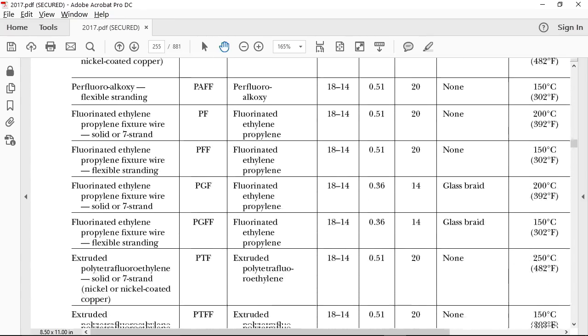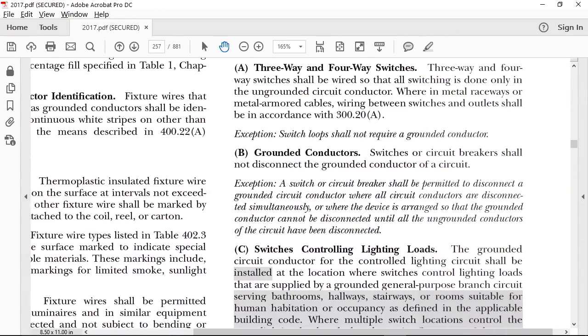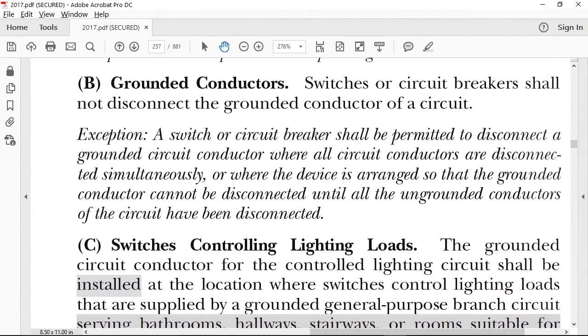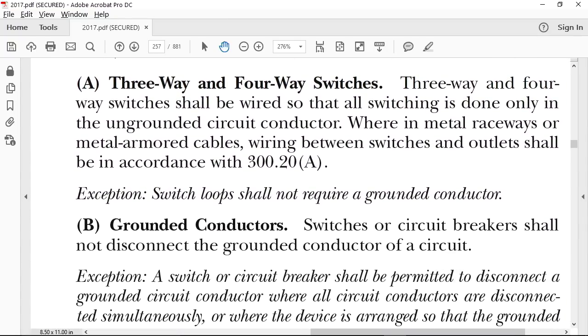Let's take a look at 404.2A - I'm wondering if that only applies to non-metallic raceways or non-metallic wiring methods. Three and four-way switches should be wired on ungrounded conductors. When using metal raceways or metal-armored cables, wiring methods shall be in accordance with 300.20(A), which deals with inductive heating to ensure canceling of conductors. The exception simply states that you don't need to have a neutral conductor in that cable.